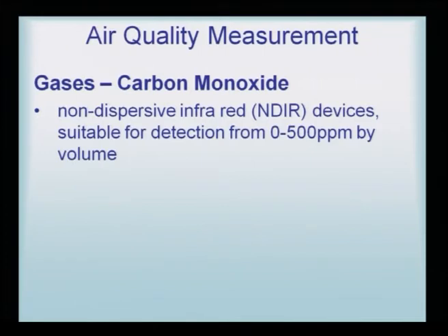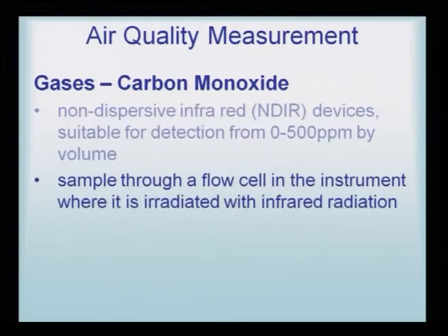Continuing with air quality measurement, the analysis of carbon monoxide has to be done in a very specific manner. Non-dispersive infrared NDIR devices are more suited for detection of 0 to 500 ppm by volume. The SOx and NOx could be done by UV method, but carbon monoxide requires a non-dispersive infrared device. The sample passes through a flow cell in the instrument, where it is irradiated with infrared radiation.